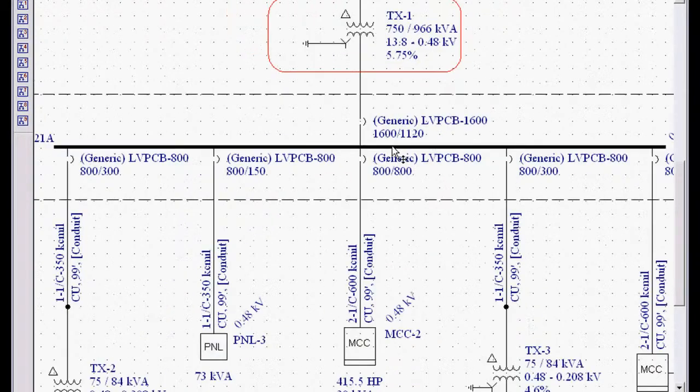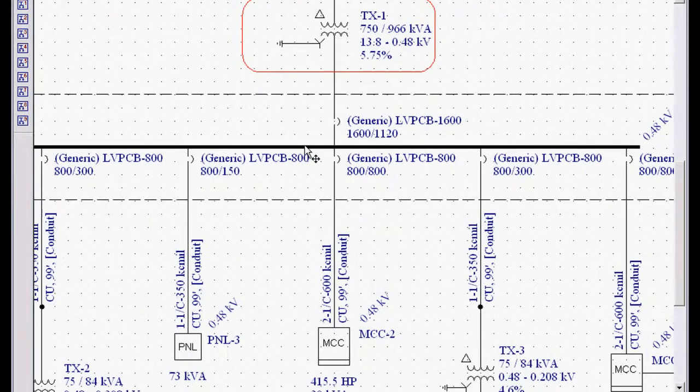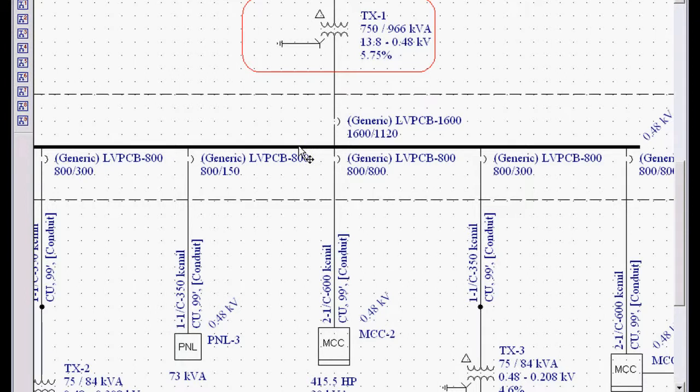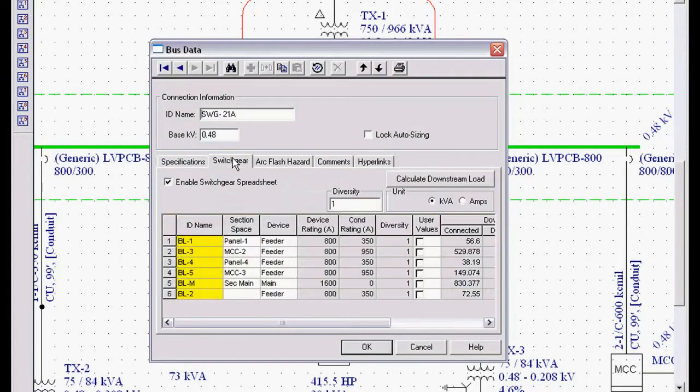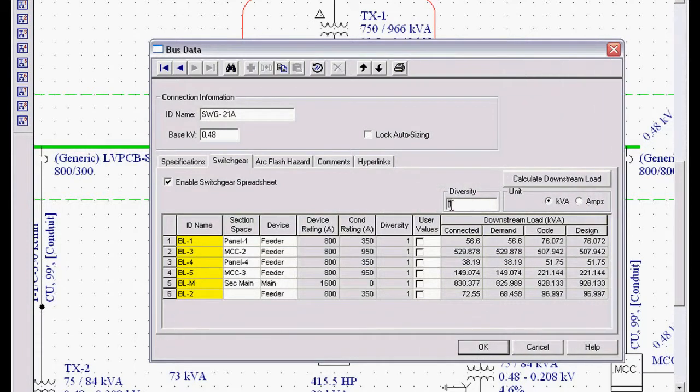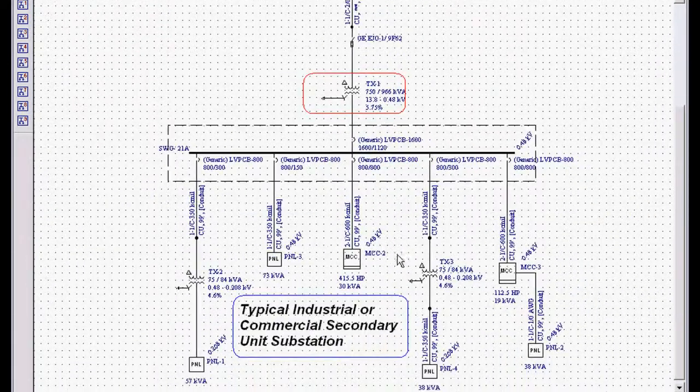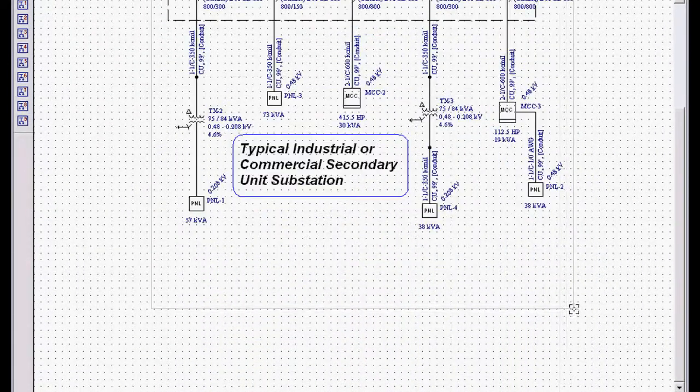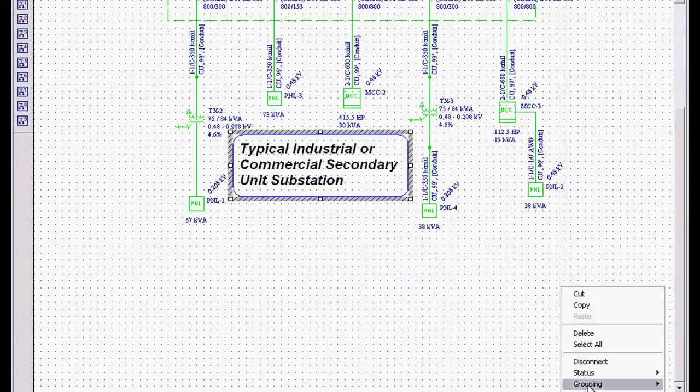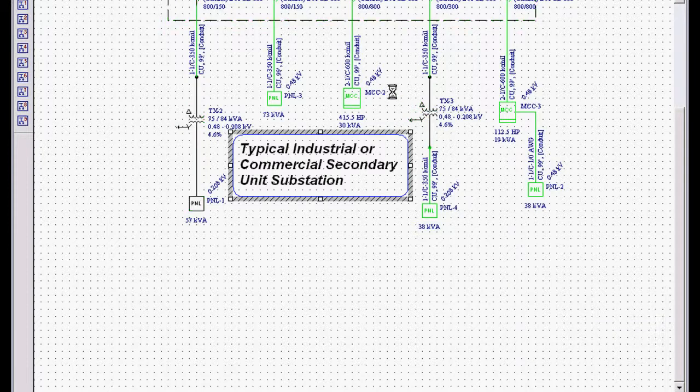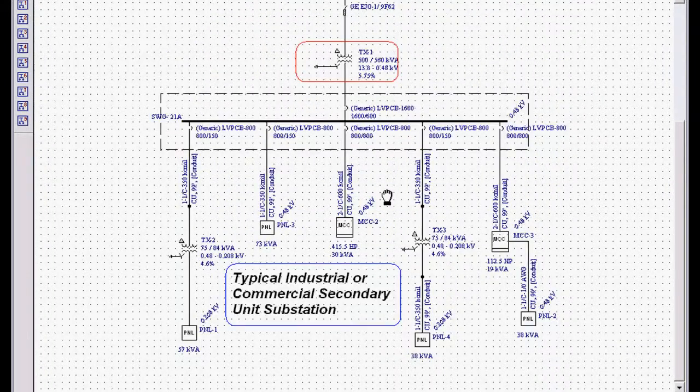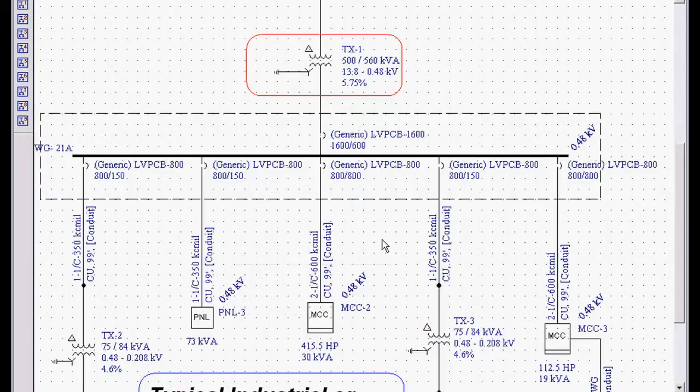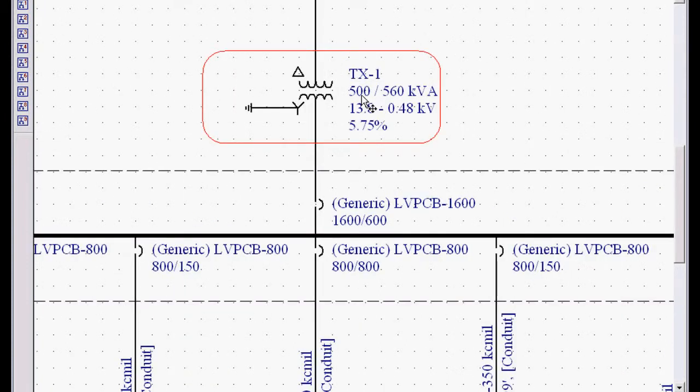Let's take a look at another function. Let's say we want to design for diversity. If we double click on this, go to our switchgear lineup and we change our diversity to 2. We click OK and we redesign. Right mouse click, auto design. Now you can see with a 2 diversity, we've stepped down from a 750 kVA transformer to a 500 kVA transformer.